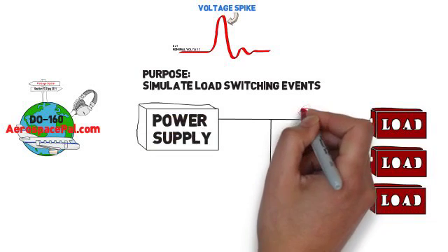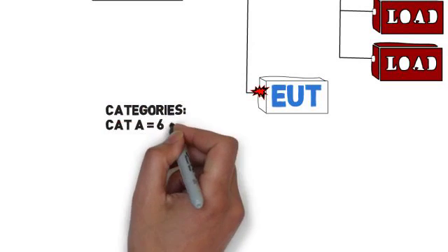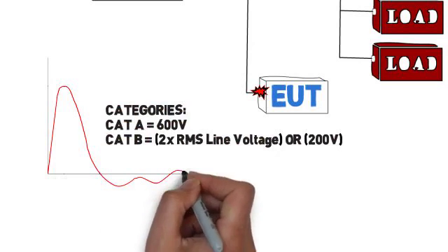There are two categories for this section: CAT A and CAT B. CAT A is tested to 600V, while CAT B is two times the line voltage RMS or 200V, whichever is the lesser of the two.